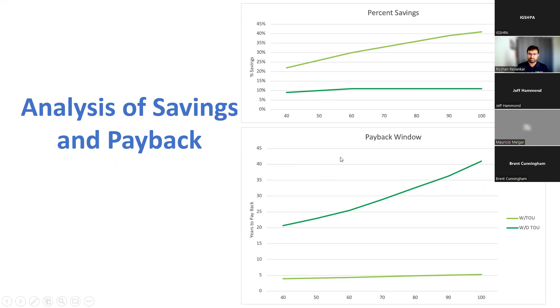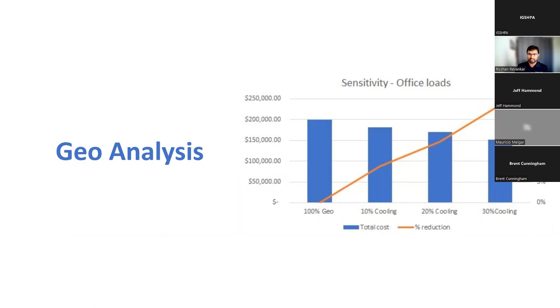How did that compare to our Geo system? Our goal was to cost-reduce Geo, and we dropped it from 40 boreholes to 4 boreholes. If we were to do 100% Geo, it would probably cost around $200,000 on the Geo side. With a smaller thermal energy storage system, we were able to reduce this by almost 25% in cost. This is for an office load building in Ohio.